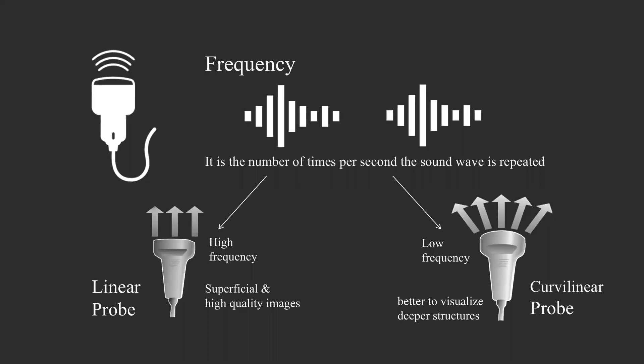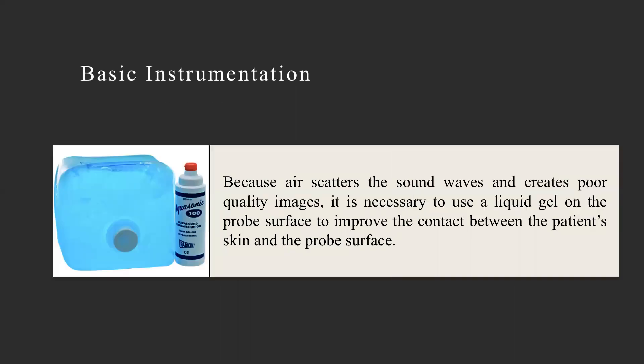Frequency is the number of times per second the sound wave is repeated. The high-frequency linear probe can visualize superficial structures with high quality. The curvilinear or abdominal probe is low frequency and gives better visualization of deeper structures, but with lesser quality for superficial structures. You need to know which probe to use during each examination. There is also the echo probe used for echocardiography.